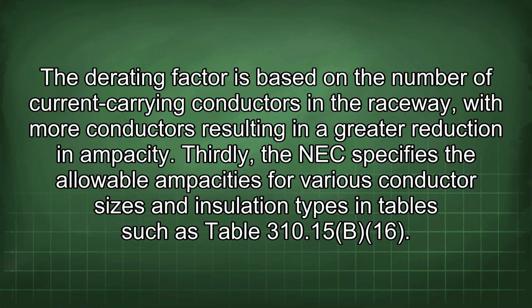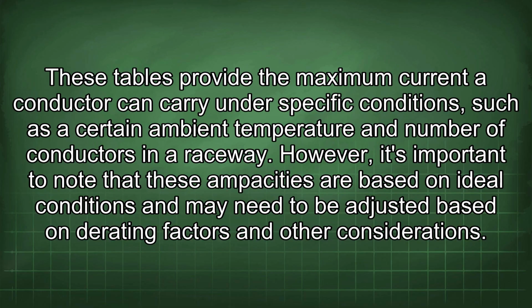Thirdly, the NEC specifies the allowable ampacities for various conductor sizes and insulation types in tables such as Table 310.15(B)(16). These tables provide the maximum current a conductor can carry under specific conditions, such as a certain ambient temperature and number of conductors in a raceway. However, it's important to note that these ampacities are based on ideal conditions and may need to be adjusted based on derating factors and other considerations.